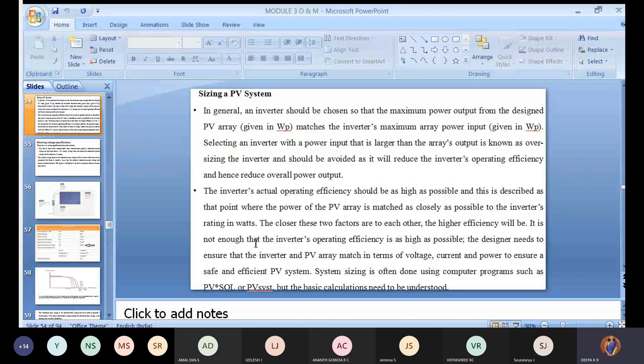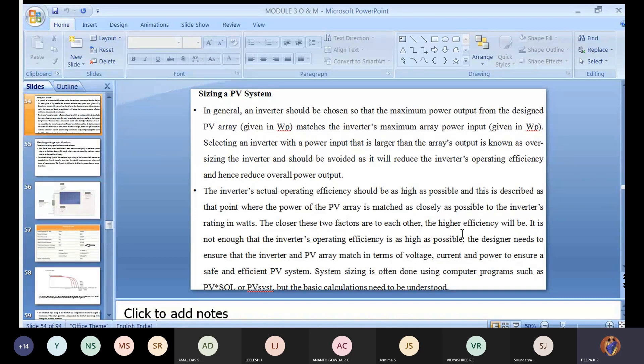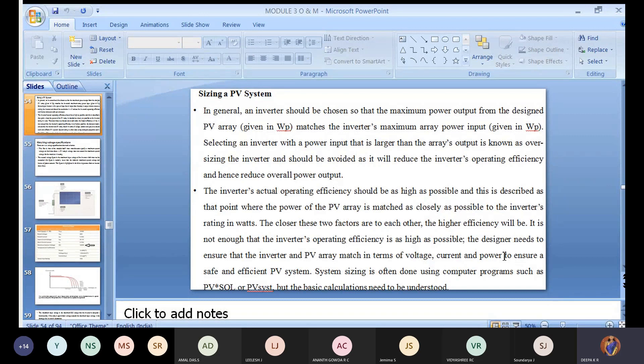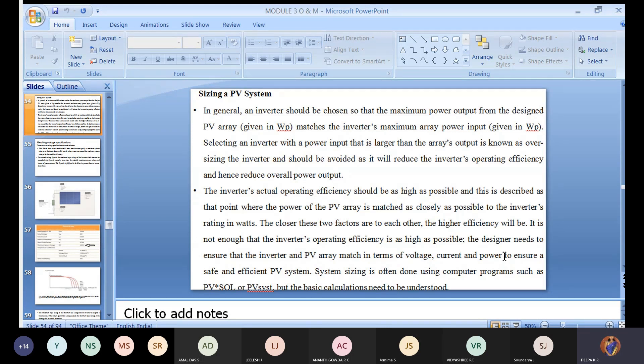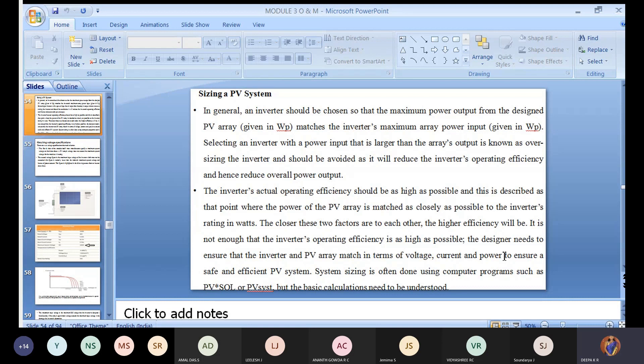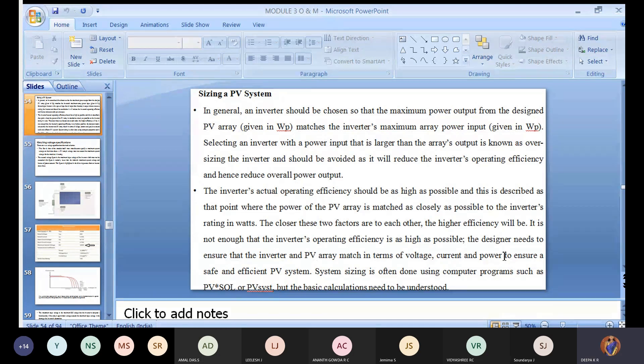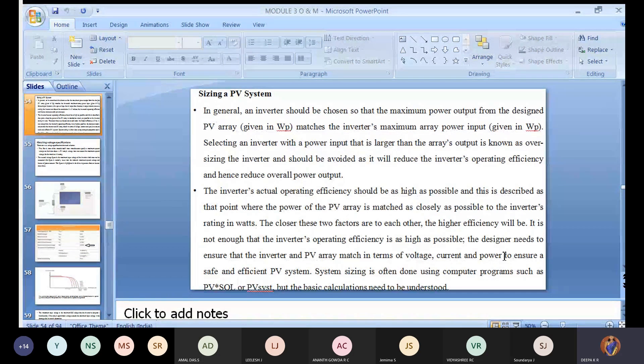It's not enough that the inverter operating efficiency is as high as possible. The designer needs to ensure that the inverter and the PV array match in terms of voltage, current and power to ensure a safe and efficient PV system. We already know the term paralleling or synchronization. Normally a generator will be synchronized with a grid system matching voltage and current. I can't speak about frequency because we have DC and AC. But you're going to match up both the PV module and the inverter considering voltage, current and power.